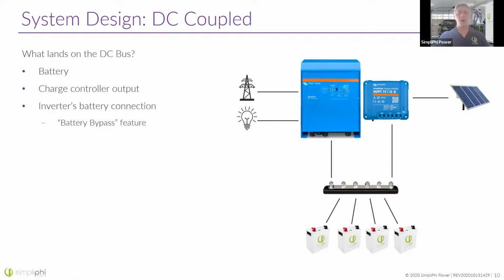So what lands on the DC bus when you're DC coupling? Let's look at the system design. First off, of course, the battery is going to land on the DC bus. So you know how to parallel wire SimpliPhi batteries, all same length, same gauge cable, of course, so the lithium batteries can be well balanced. But did you know that the charge controller and inverter also land on that DC bus? So this is going to allow the charge controller to push and pull power from the battery bank, and at the same time, the inverter can draw power from that same DC bus as well.